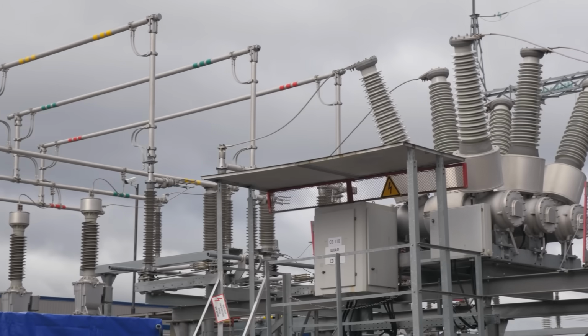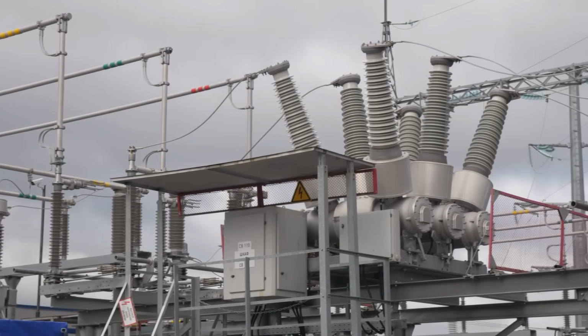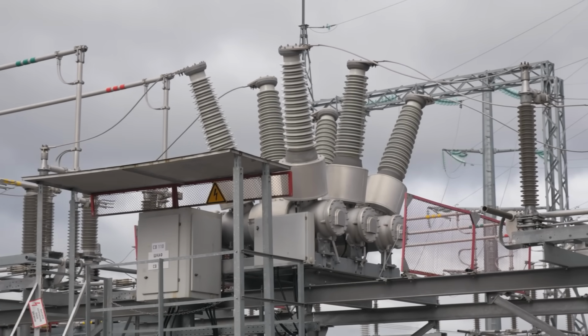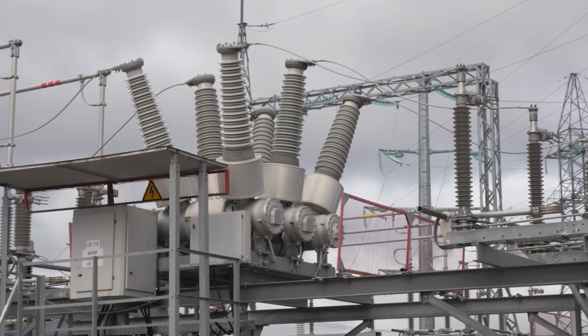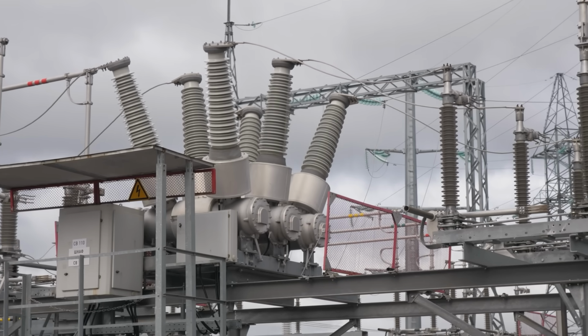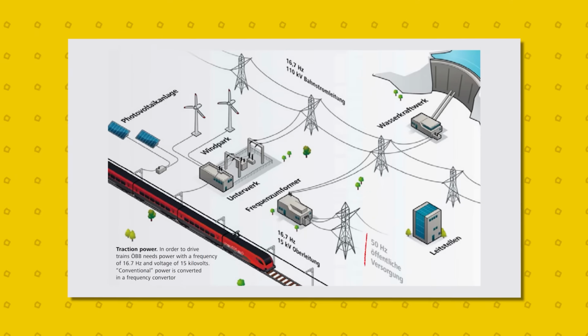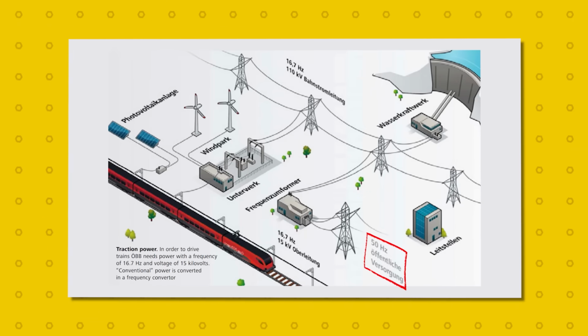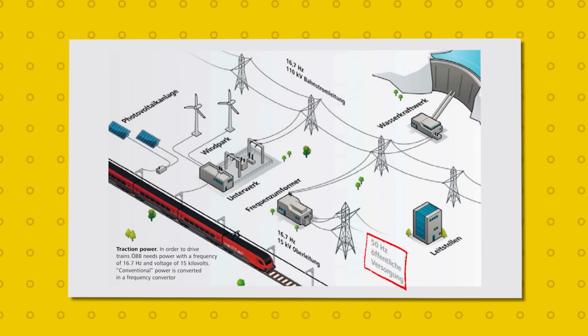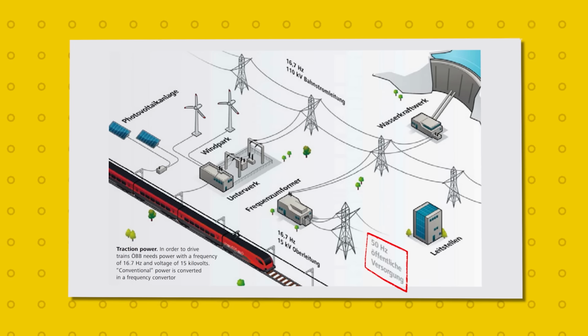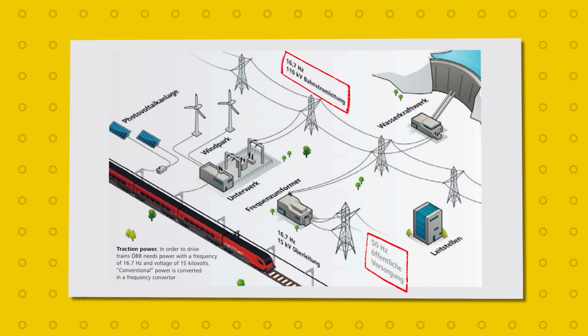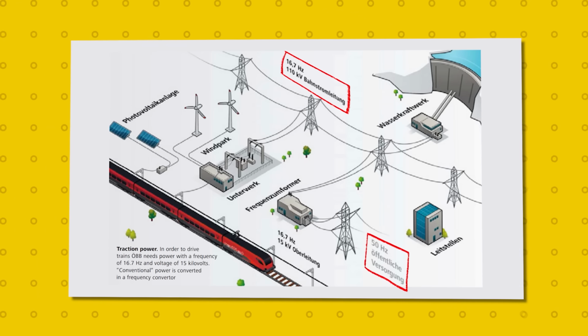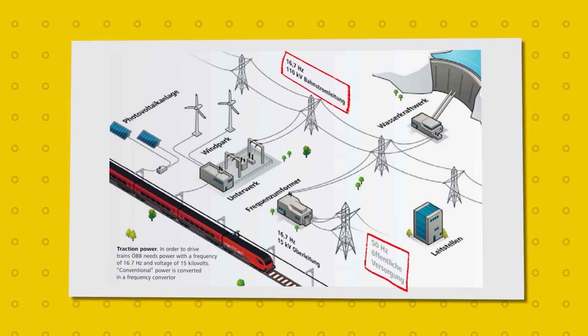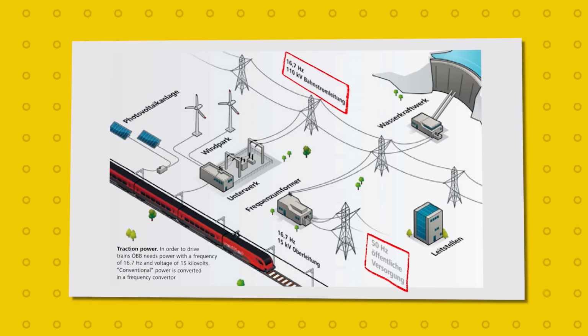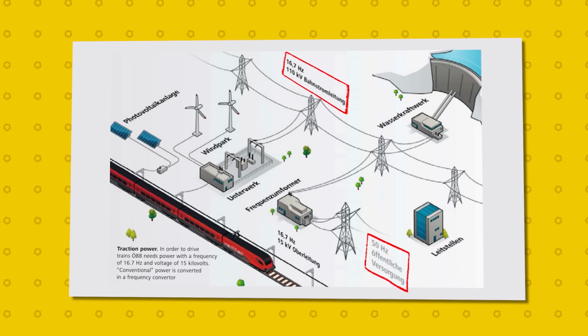This is done at 8 converter stations run by ÖBB Infrastruktur, including key sites in Selstal and Langenwang. These converter facilities receive 50 Hz electricity from the National Transmission Network or ÖBB's own generation sources and convert it to 16.7 Hz. At the same time, the voltage is stepped up to either 55 kV or 110 kV.